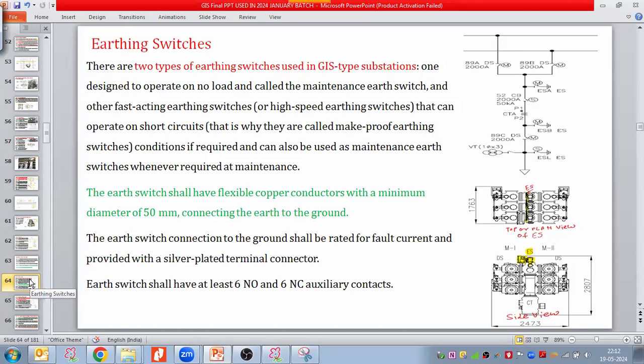Now coming to the earthing switch, and why we take the earthing switch and the types of earthing switch. There are two types of earthing switch used in GIS type substations. In case of the AIS, we take a single type of earthing switch, which is the maintenance earthing switch. But when it comes to the GIS, we take two types of earthing switch in the GIS substations. One is designed to operate on no load conditions, and that is called the maintenance earthing switch. And the second earthing switch is the fast acting earthing switch, or sometimes we call it a high speed earthing switch, that can operate on short circuit condition as well. That is why they are called make proof earthing switches.